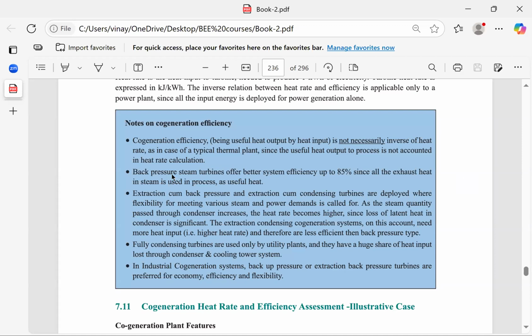There are certain exceptions to that. Useful heat output divided by heat input is not necessarily the inverse of heat rate. Heat rate calculations are based on the losses, how much we are losing. Whereas the overall efficiency of a cogeneration system directly gives you the useful heat output divided by the total input.